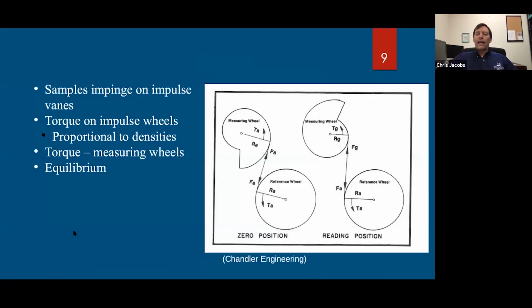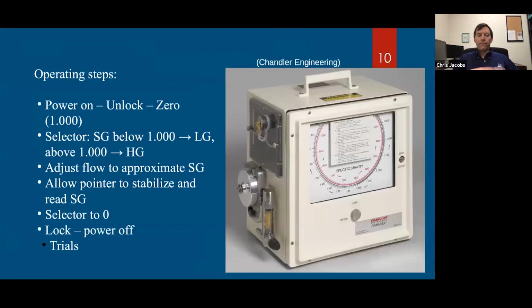So remember, it is the torque that makes the adjustment, not necessarily the forces. So how do we actually use the machine? I'm just going to go over this briefly in a discussion form, and then I will show you the video. The first thing you want to do, obviously, is to power the unit up. If you're using AC, you plug it into your AC supply. If you're using DC, you first power up your inverter.